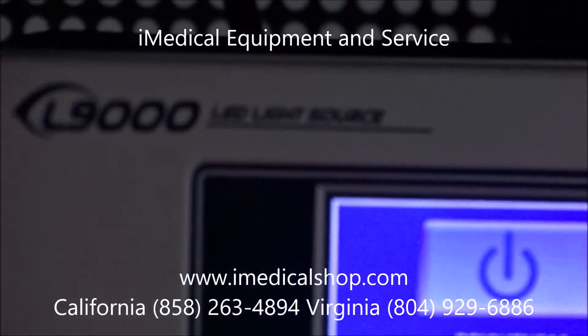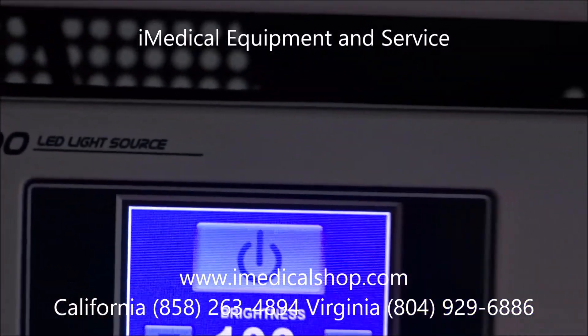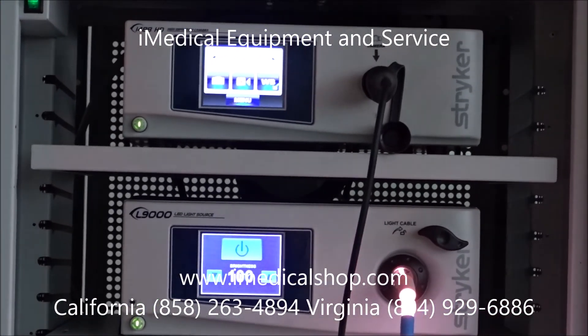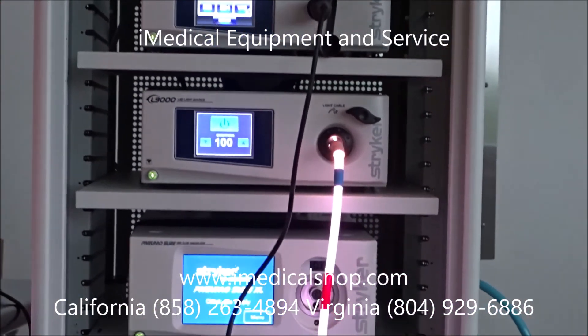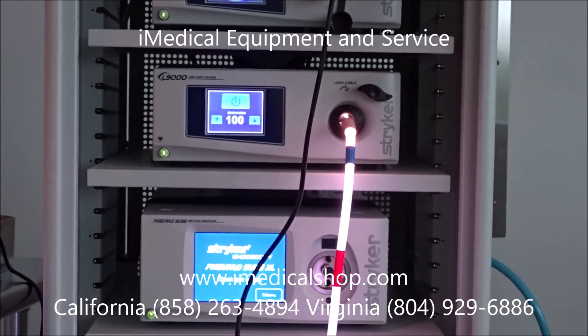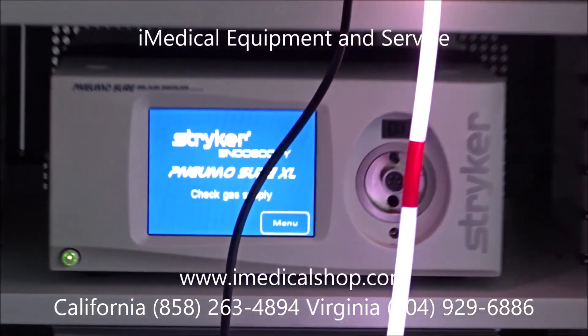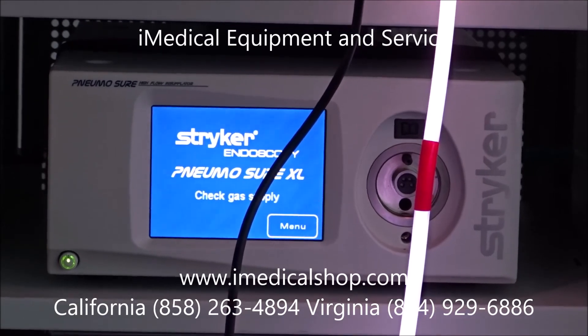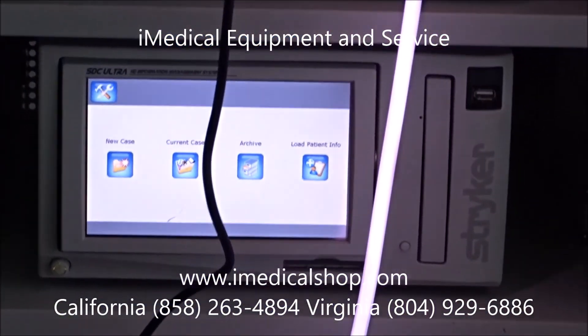This is the L9000 light source, found on the newer systems. Right below that you've got your insufflator, and the insufflator runs carbon dioxide into the abdominal area to open it up and make it easier to maneuver the camera.